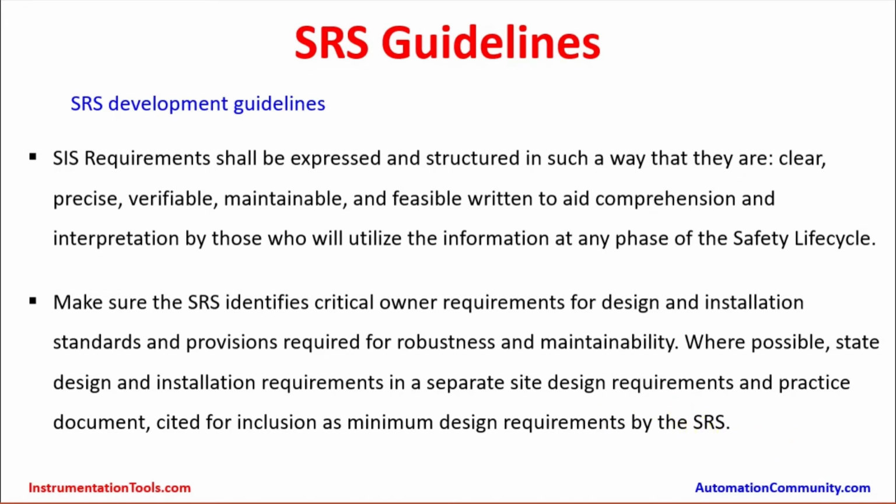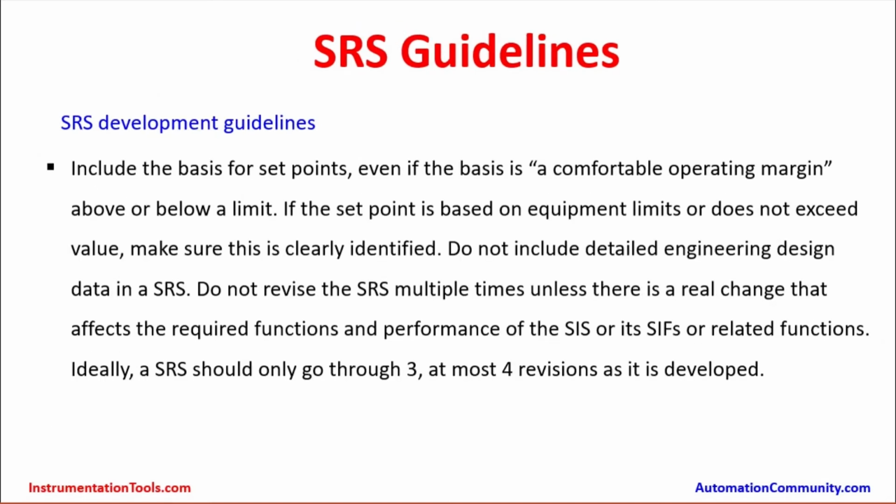So the design and installation standard requirements have to be updated, and that has to be reviewed. Now include the basis for set points, even if this basis is a comfortable operating margin above or below a limit. If the set point is based on equipment limits and does not exceed a value, make sure that it is clearly identified. Do not include detailed engineering design data in the SRS.